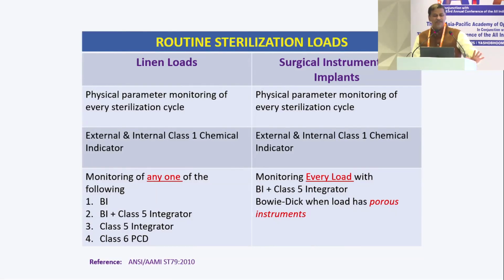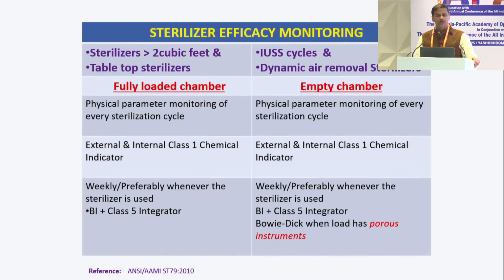So now let's see what are the indicators that should be used. Suppose you want to just sterilize your routine loads, that is linen, and surgical instruments: the first 2 columns are the same. That is a physical parameter monitoring and a class 1 tape stuck outside. For a linen load, any one of these 5 is enough. But if you're using surgical instruments and an implant, then you need to have a biological indicator and a class 5 for every load. You have to monitor the efficacy of the sterilizer.